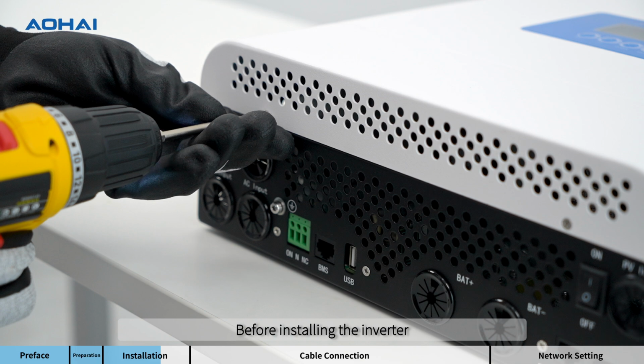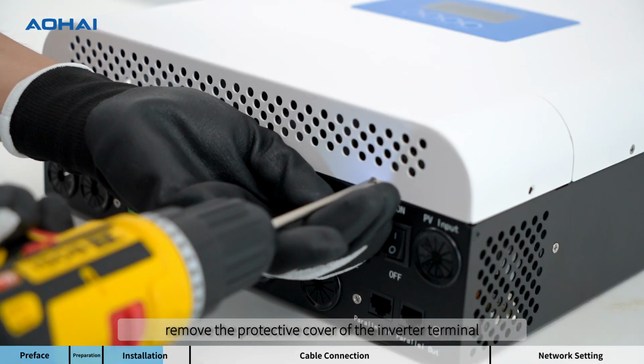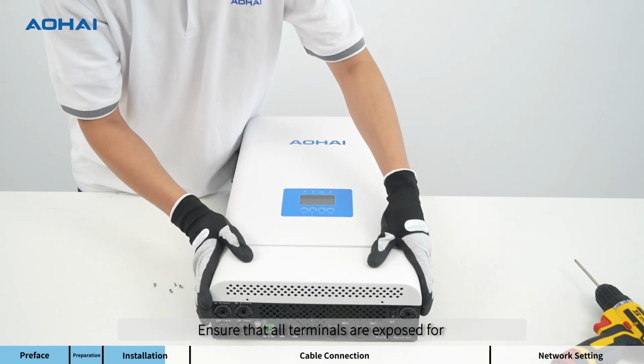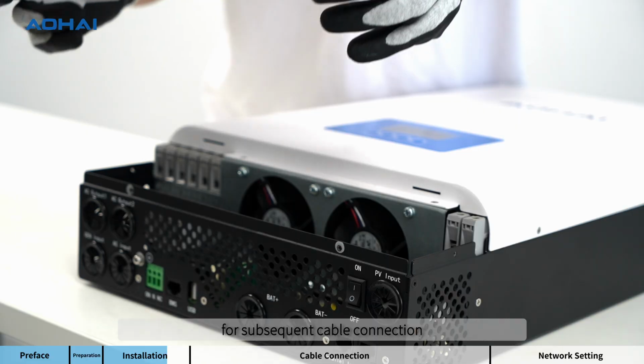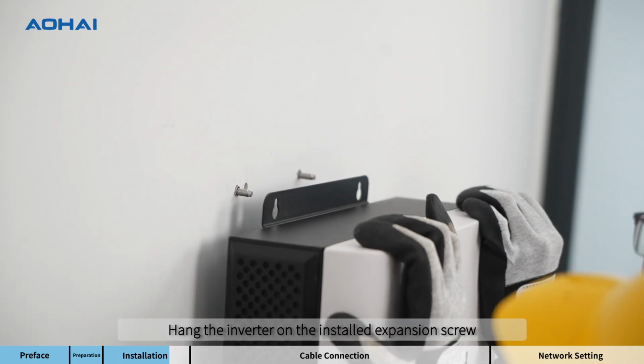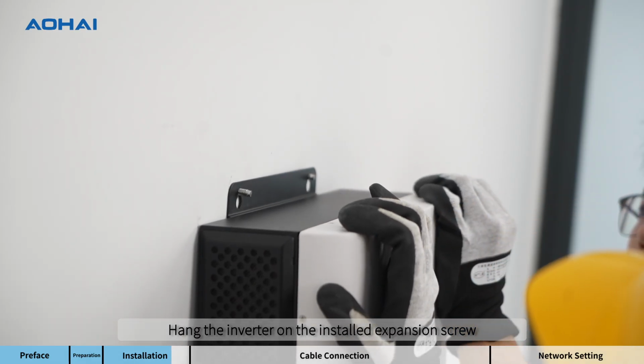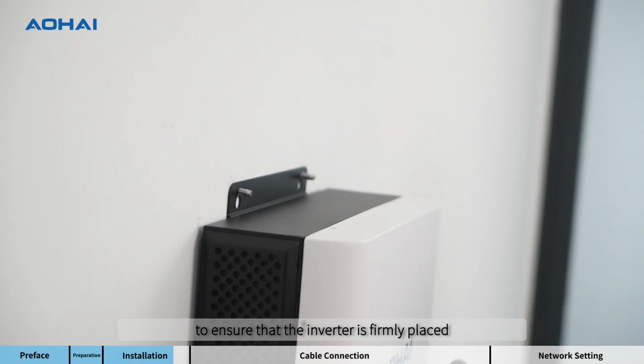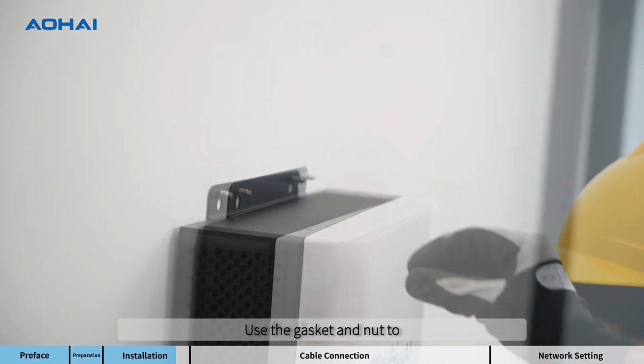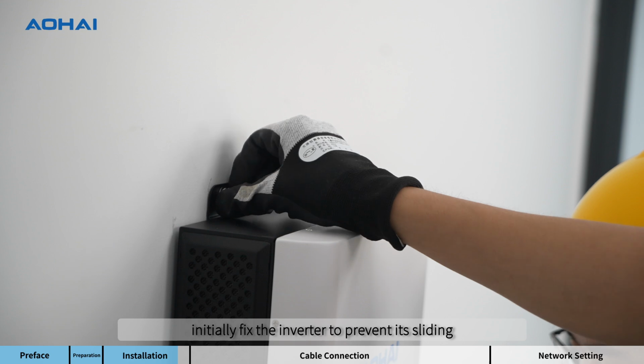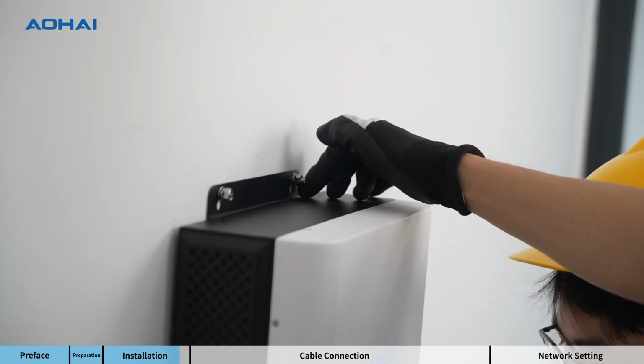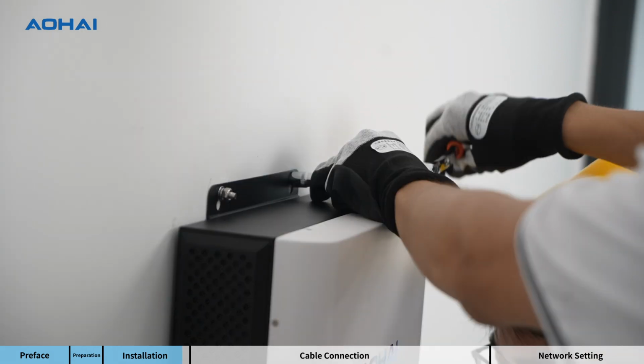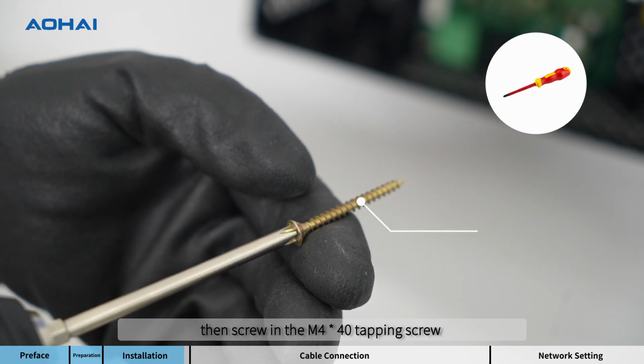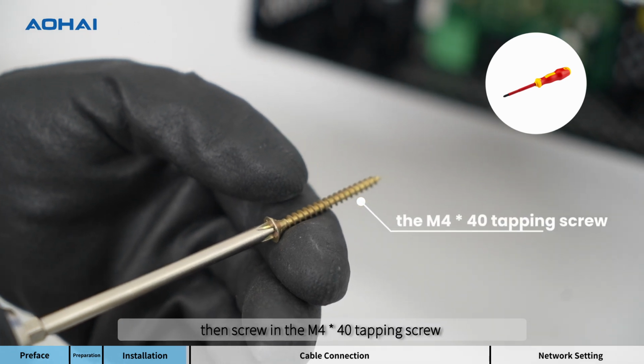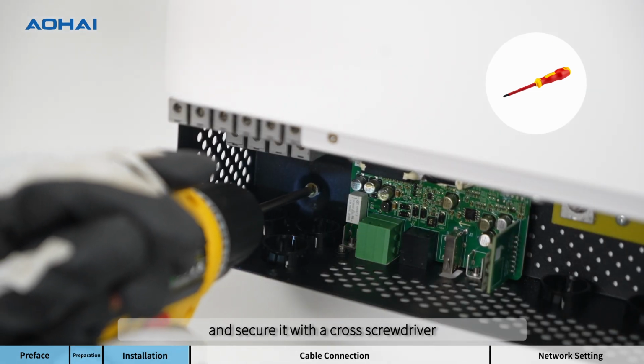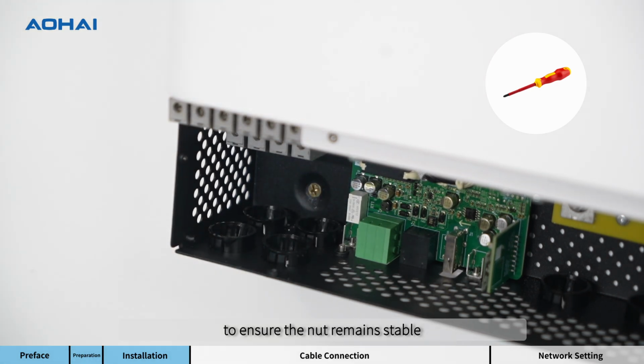Before installing the inverter, remove the protective cover of the inverter terminal. Ensure that all terminals are exposed for subsequent cable connection. Hang the inverter on the installed expansion screw to ensure that the inverter is firmly placed. Use the gasket and nut to initially fix the inverter to prevent it sliding. Then screw in the M4*40 tapping screw and secure it with a cross screwdriver to ensure the nut remains stable.